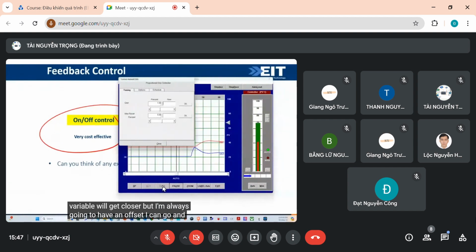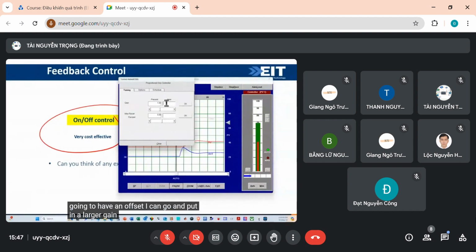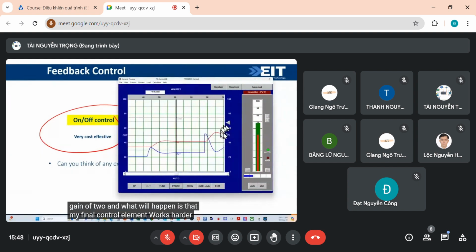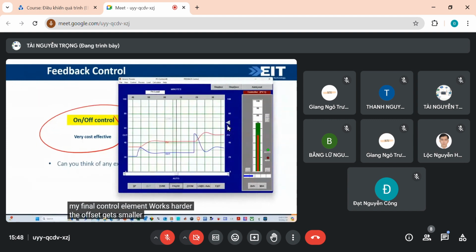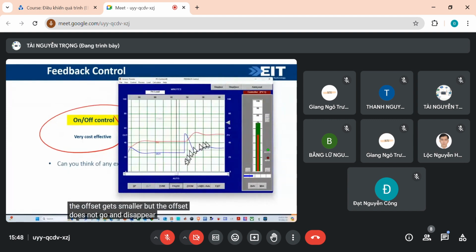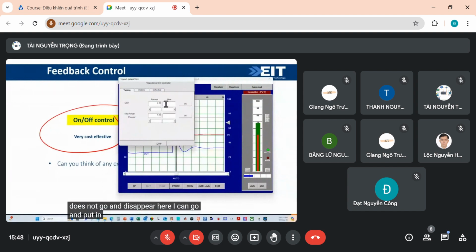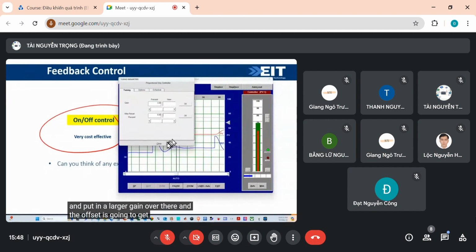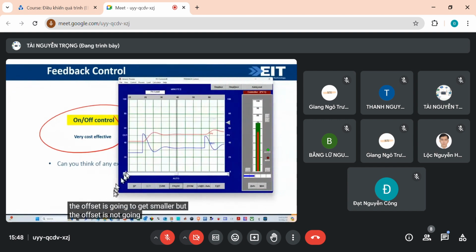I can put in a larger gain - let's set a gain of 2. What happens is that my final control element works harder, and the offset gets smaller, but it does not disappear. I can put in an even larger gain, and the offset will get smaller still, but it's not going to disappear.